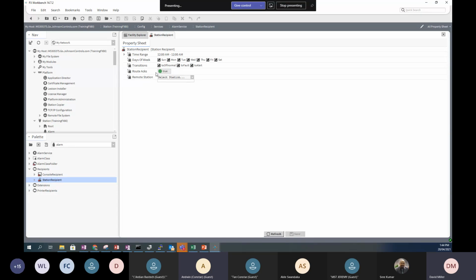And then you have route acknowledge is true. Right. The thing is, if we have a single alarm point, we test it out, no issue and no problem itself. But when the alarms come in bunch, like 5, 10, or sometimes more than that, multiple times, sometimes it will be missed out. It doesn't clear and there's a leftover.